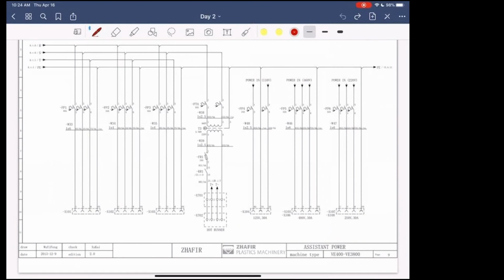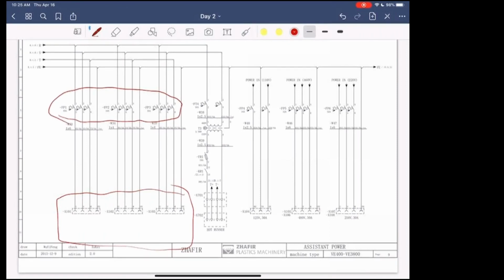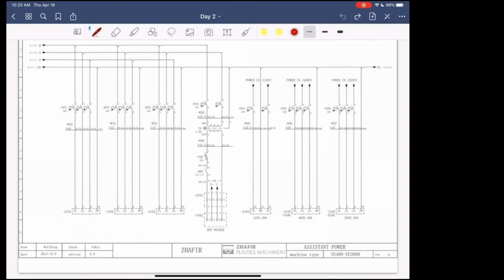Assistant power sockets: below the injection unit, there's a cabinet. Inside the cabinet, there's a box. The box has these assistant power socket connectors. It's actually on a 30 amp and two 16 amp breakers. The problem is these are not calculated in the full load amperage of the machine because technically they're not installed. They're just there in case the customers want to use them. You can actually break into the circuit and install a 30 amp plug, 3-phase, or two 16 amp plugs.